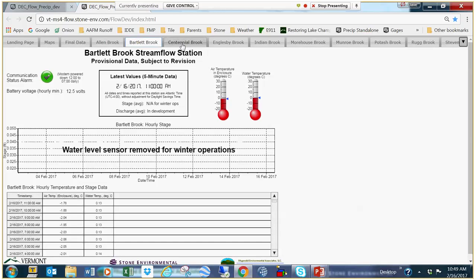So that instrument's pulled, but you can see we're still getting the air temperature and water temperature. The water temperature is actually recorded on the pressure transducer, which is stuck in the conduit well above the water level to protect it. So for sites where the sensor's been removed, that 'water level' is actually just the air inside the conduit.